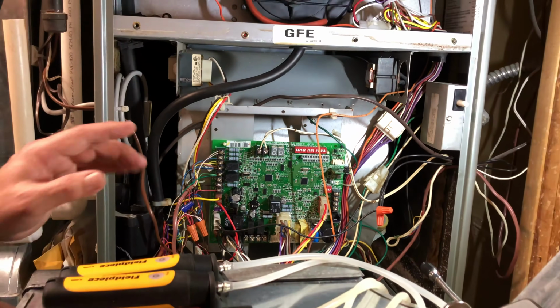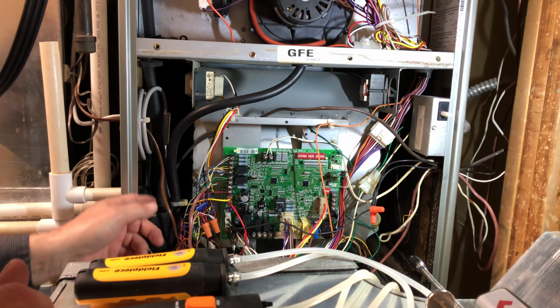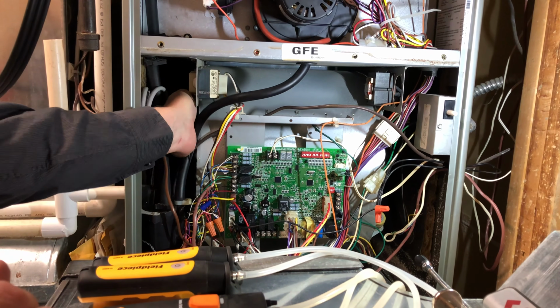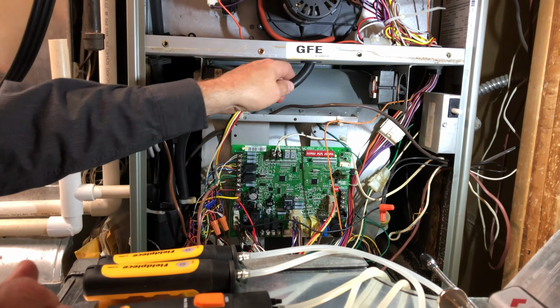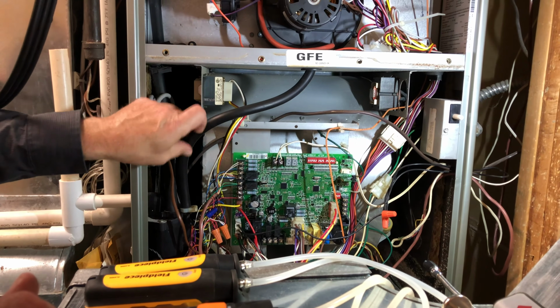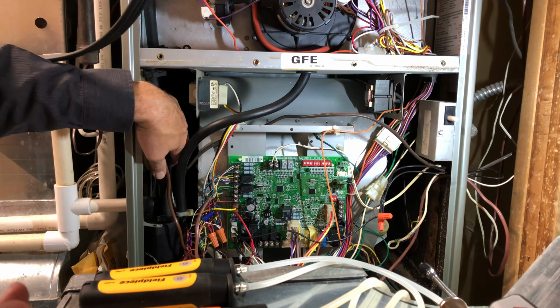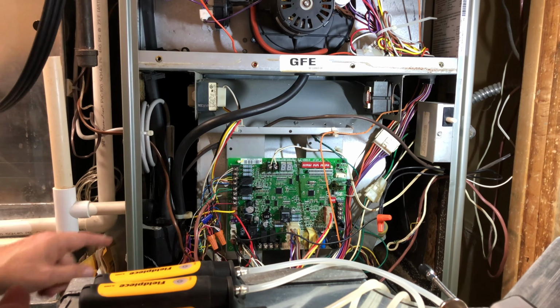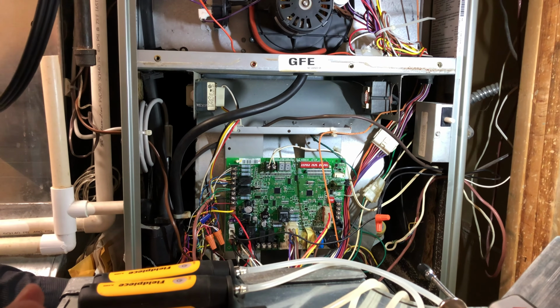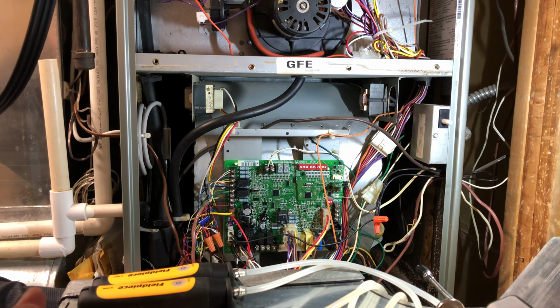So it's a really handy thing when you're trying to get the furnace set up, just to set it into a test mode. I can check my blower, make sure my blower's good and clean. I inspect these hoses here on the traps. These, a lot of times, will get corroded, so you want to just give everything a little bit of tug and pull and make sure everything's still connected nicely. Look for evidence of water leakage down in the bottom of the furnace, which there doesn't appear to be any.